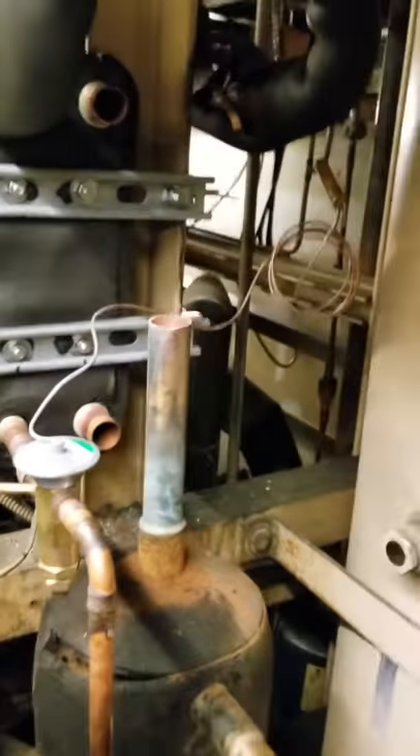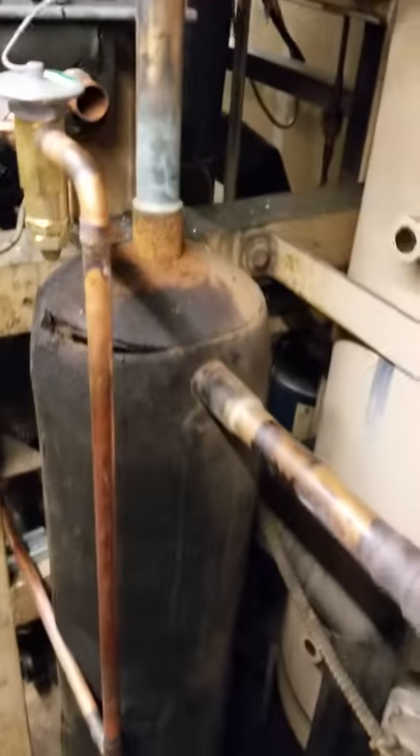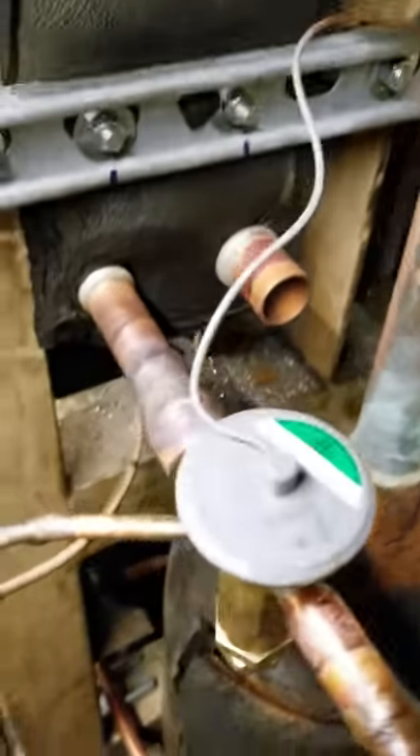TI Refrigeration and HVAC Scoop — here we go. We're changing out a five-ton subcooler today, taking out the barrel type and putting in a flat-plate subcooler. We're using the Sporlan Y1155VC valve, a 5 to 30-ton valve — recommended.